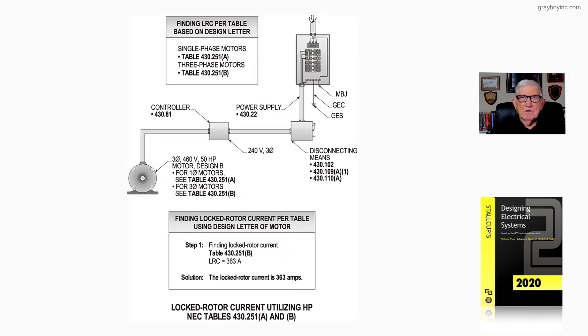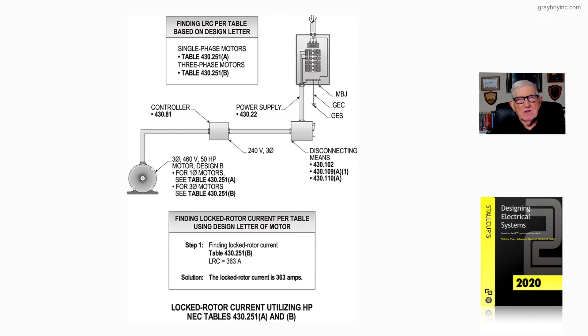To do this, we would have to go to page 10 in the NEC, look at section 430.7A9, and it gives the permission there to use the design letters if we wish to do so, and it would work out in our design to start the motor and accelerate the load. And we would go to table 430.251 on page 334 of the code.